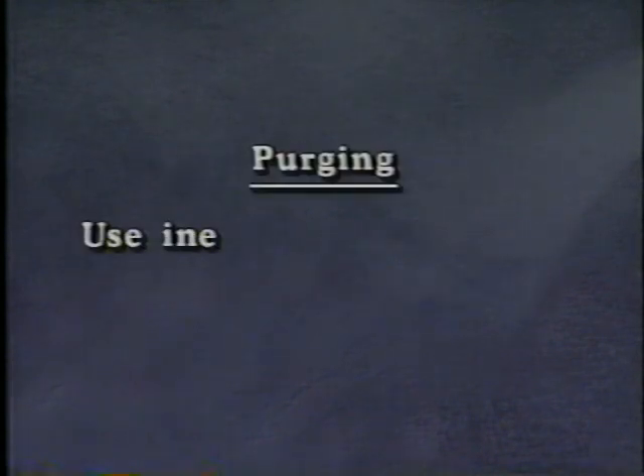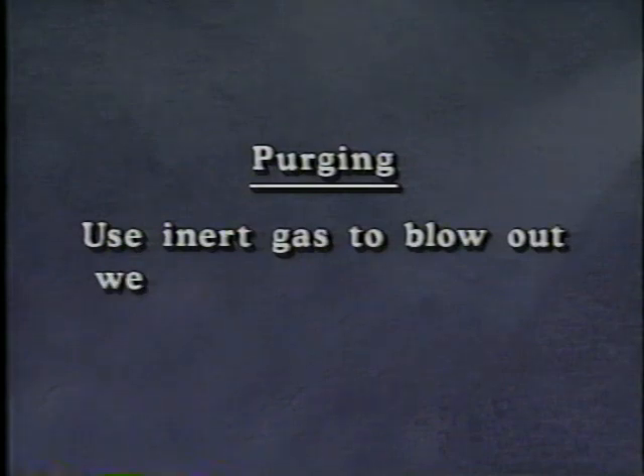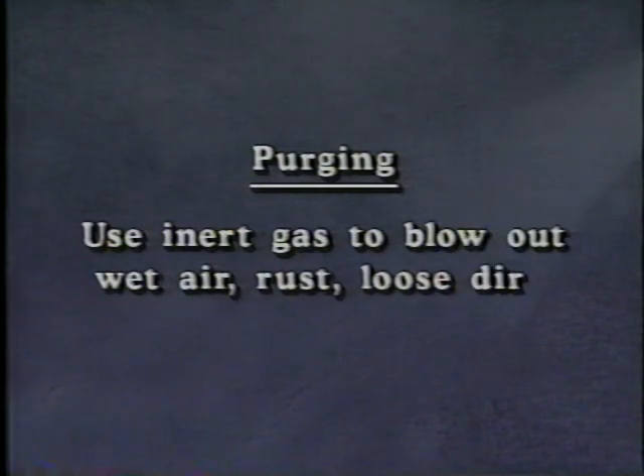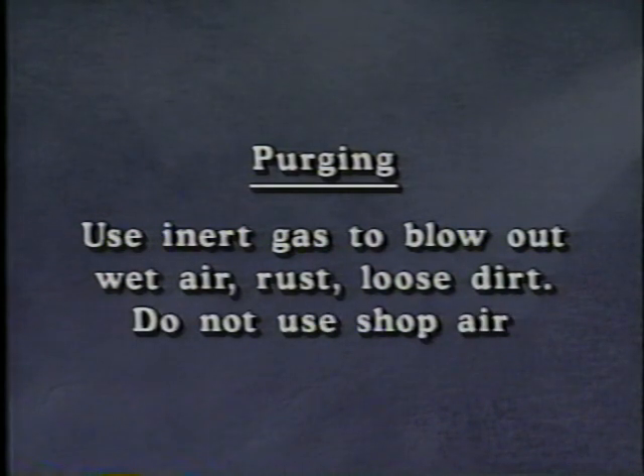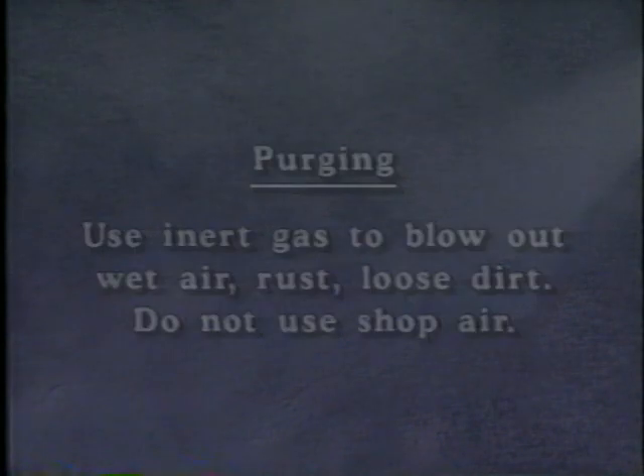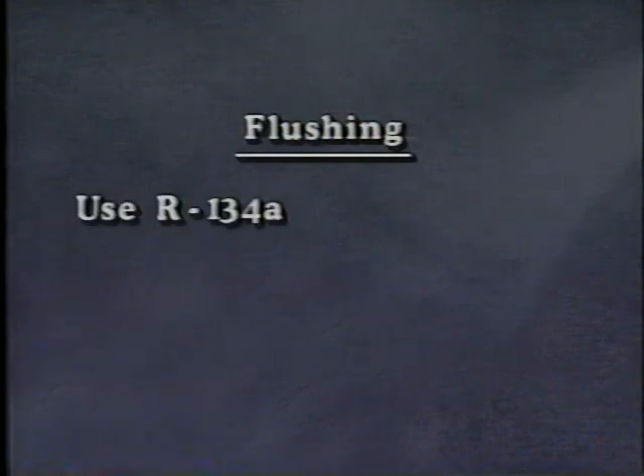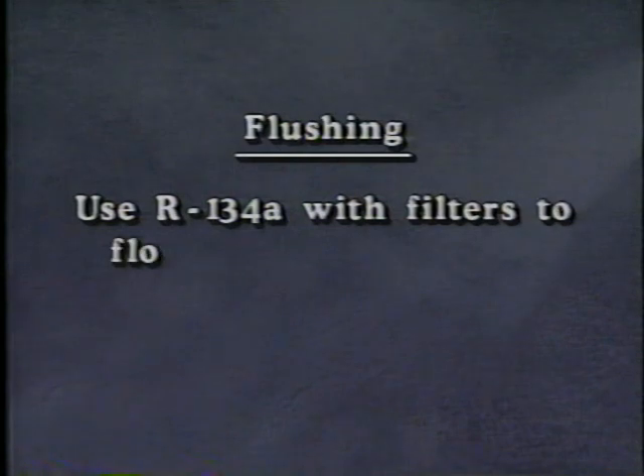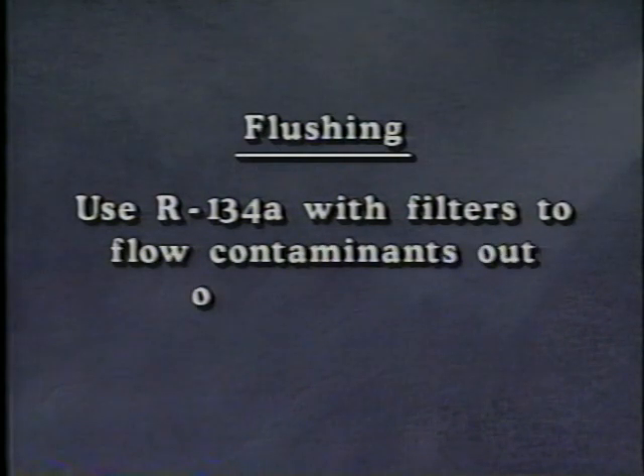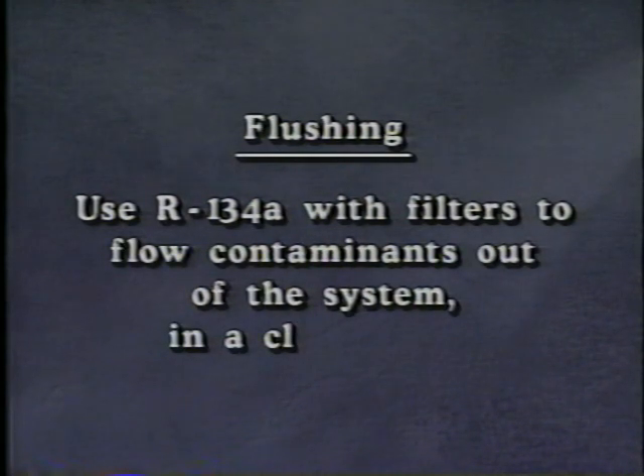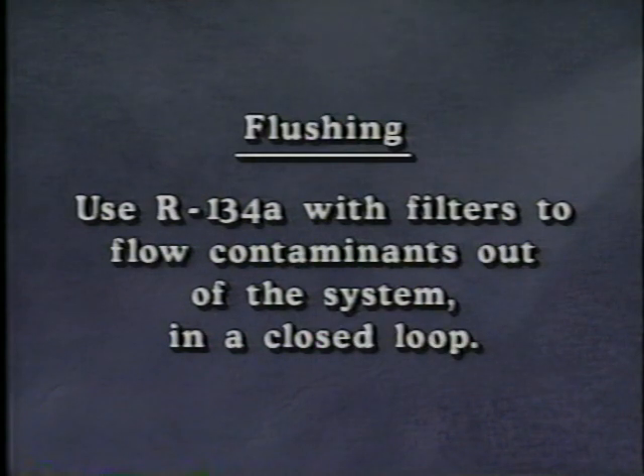Purging involves the use of a dry, inert gas, such as nitrogen, to blow out wet air, rust, or loose dirt from the plumbing. Do not use shop air. Flushing, which is reserved for extremely contaminated systems, involves the use of liquid R134A under pressure. R134A is pushed through the system, and filters are used to remove contaminants. The R134A is returned to a refrigerant recovery station in a closed loop.